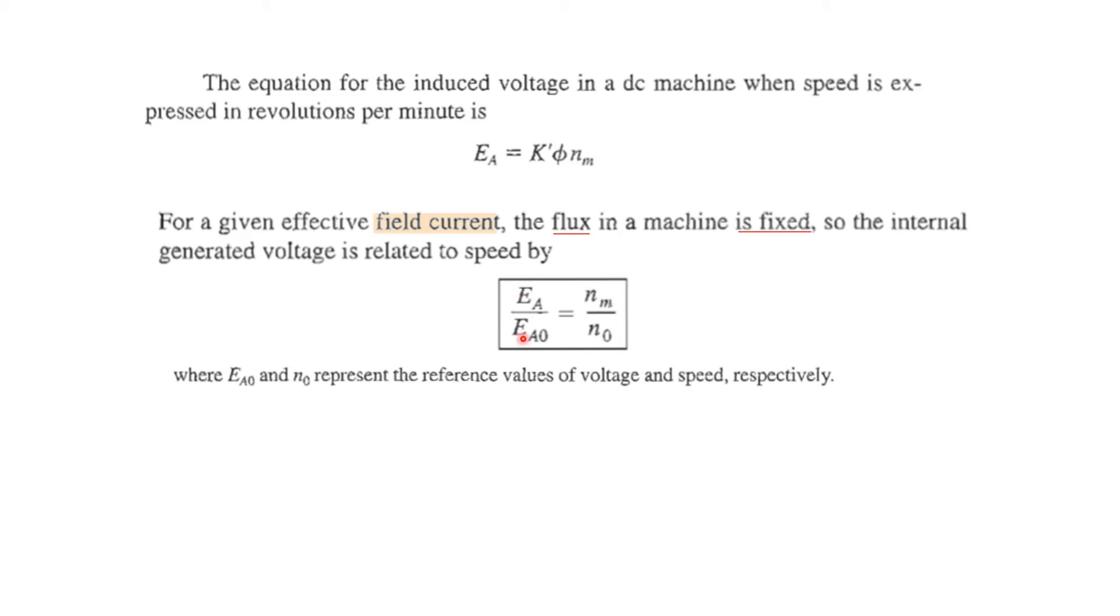And so we can derive a relationship that Ea divided by Ea naught is equal to Nm divided by N naught, where Ea naught and N naught represent the reference voltage and reference speed. So if you know the reference voltage and reference speed, then we can find any speed for a given induced voltage or we can find any induced voltage for a given speed.